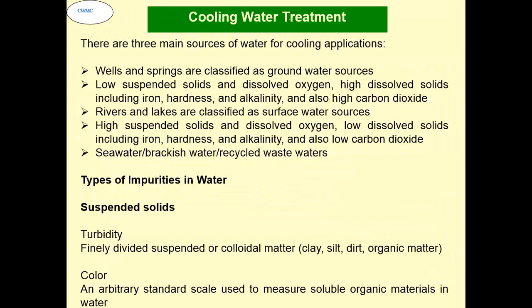There are three major water sources for cooling applications. Wells and springs have low suspended solids. Rivers and lakes are classified as surface water; they have high suspended solids and dissolved oxygen, and low dissolved solids. Seawater and brackish water have a high concentration of solids, and seawater has a very high level of chloride. Conductivity is also very high.